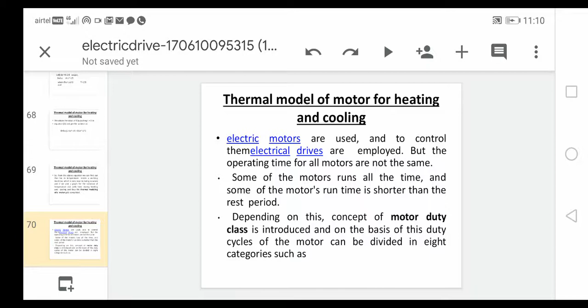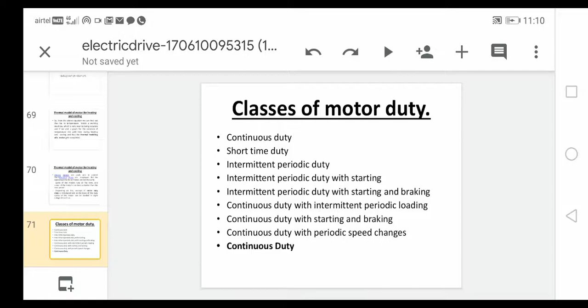Electric motors are used and controlled by electric drives, but the operating time for all motors is not the same. Some motors run all the time and some run for a time shorter than the rest period. Depending on this, the concept of motor duty cycle is introduced, and on this basis the duty of the motor can be divided into 8 categories such as continuous duty, short time duty, intermittent periodic duty, intermittent periodic duty with starting, intermittent periodic duty with starting and braking, continuous duty with intermittent periodic loading, continuous duty with starting and braking, and continuous duty with periodic speed changes.